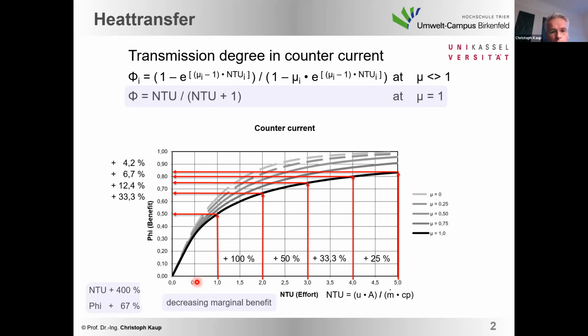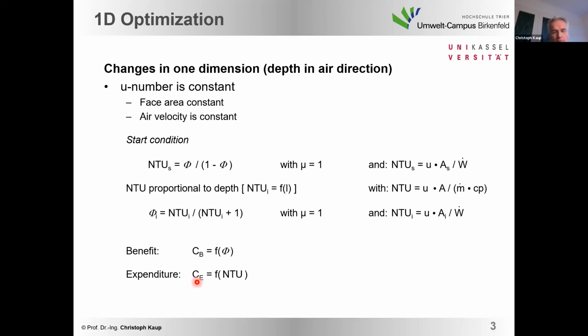So at the end, we have a plus of 400% in our effort, but only a plus of 67% in the thermal capacity. So we have a decreasing marginal benefit, but a linearly increasing effort in our heat exchanger. That is the problem, and that's the reason why we have to limit the efficiency in our heat recovery system.